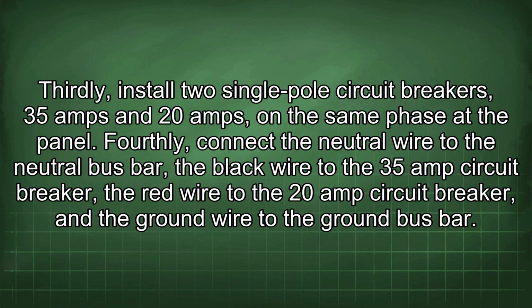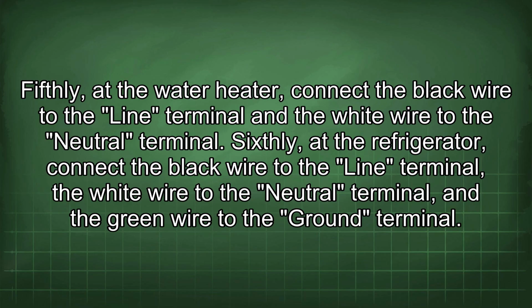Thirdly, install two single-pole circuit breakers, 35 amps and 20 amps, on the same phase at the panel. Fourthly, connect the neutral wire to the neutral bus bar, the black wire to the 35 amp circuit breaker, the red wire to the 20 amp circuit breaker, and the ground wire to the ground bus bar. Fifthly, at the water heater, connect the black wire to the line terminal and the white wire to the neutral terminal. Sixthly, at the refrigerator, connect the black wire to the line terminal, the white wire to the neutral terminal, and the green wire to the ground terminal.